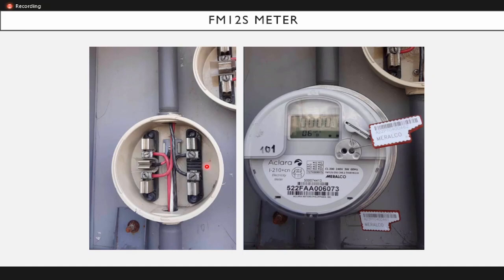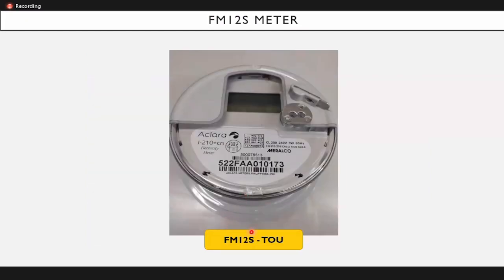Since single-phase installation, sourcing from three-phase, grounding connection should be ensured properly and correctly installed, ang mga grounding, to avoid no display of meters. This is another example of a 12S time of use meters. It's just the same with the 1S kanina. It's just that this could be used as a single-phase meter from a three-phase source.